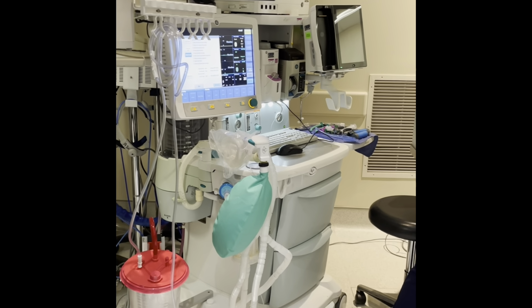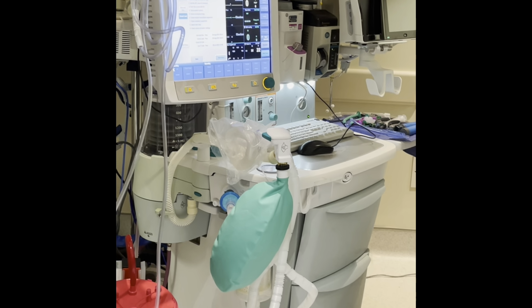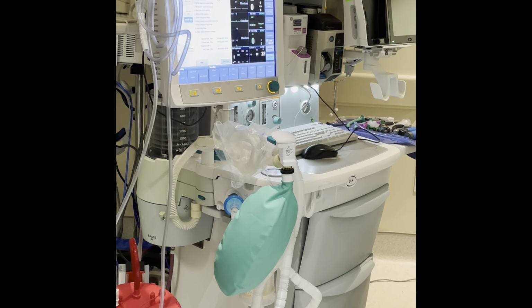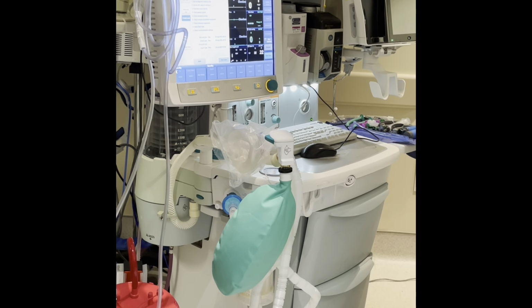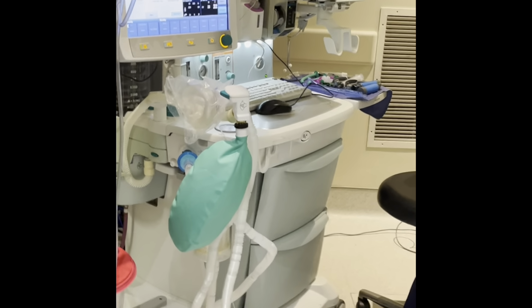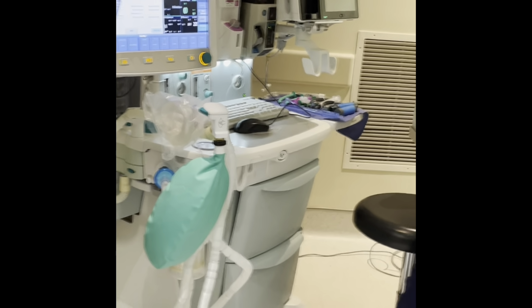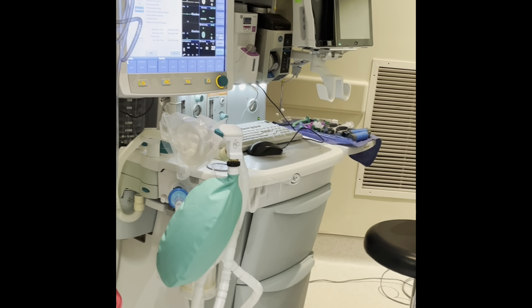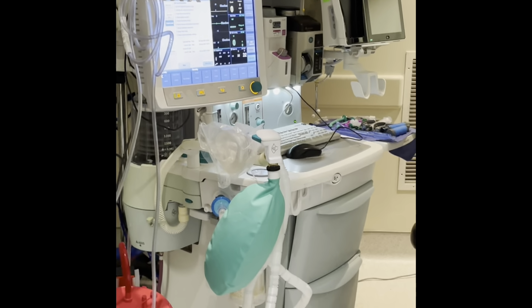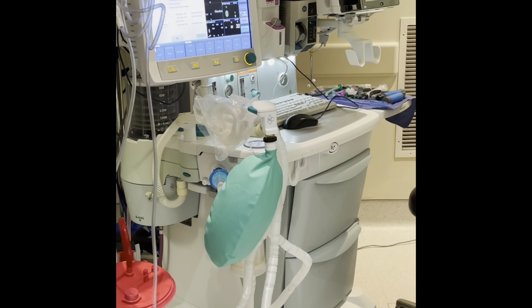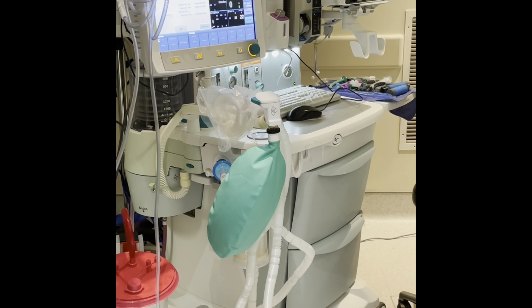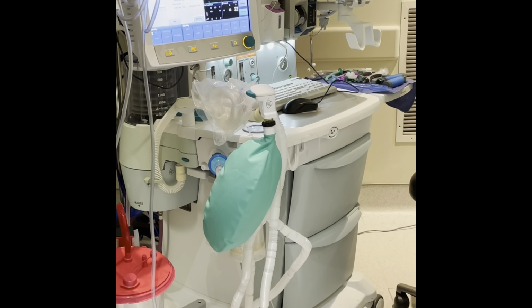So that starts at those pressure regulators and goes to the flow meter valves, and it includes the oxygen flush, it includes your vaporizers, no, the vaporizer is low pressure. It includes the pipeline, your fail-safe, what else? Anything else important? No, that's about it. And then your low pressure system is going to start at the flow meters, and that's going to go to your circle system, to the breathing circuit.